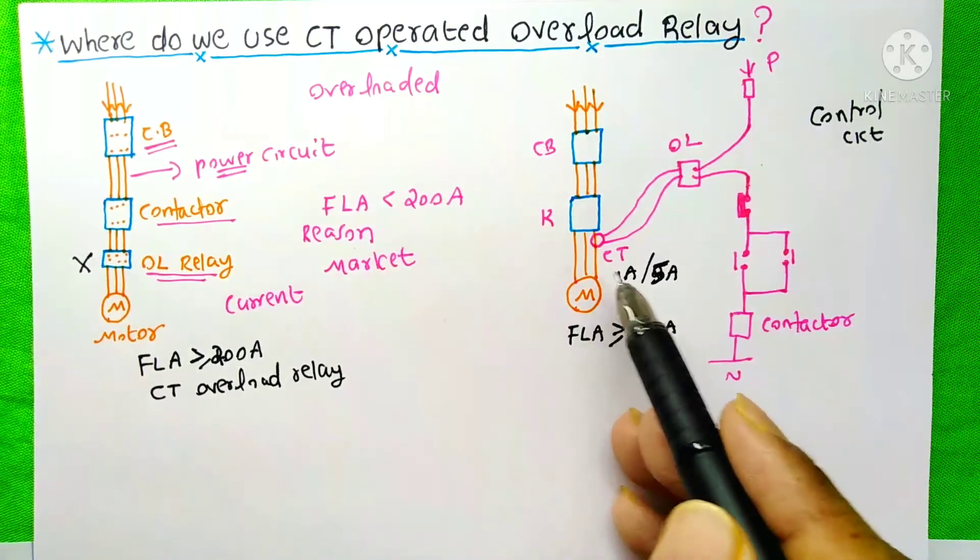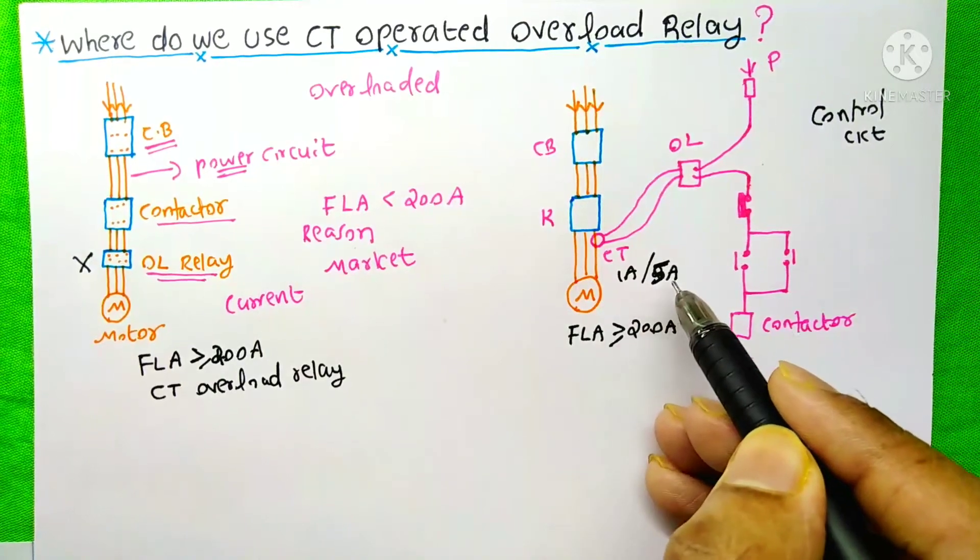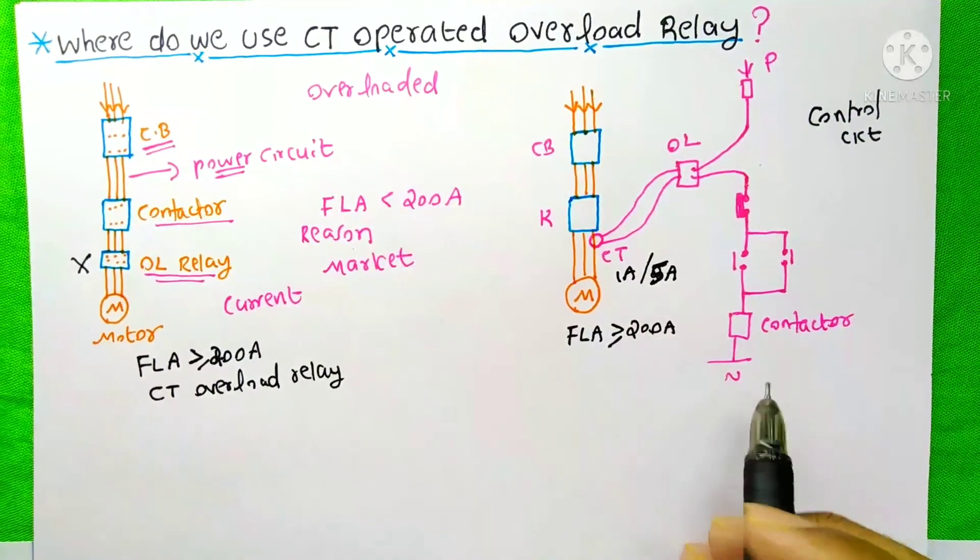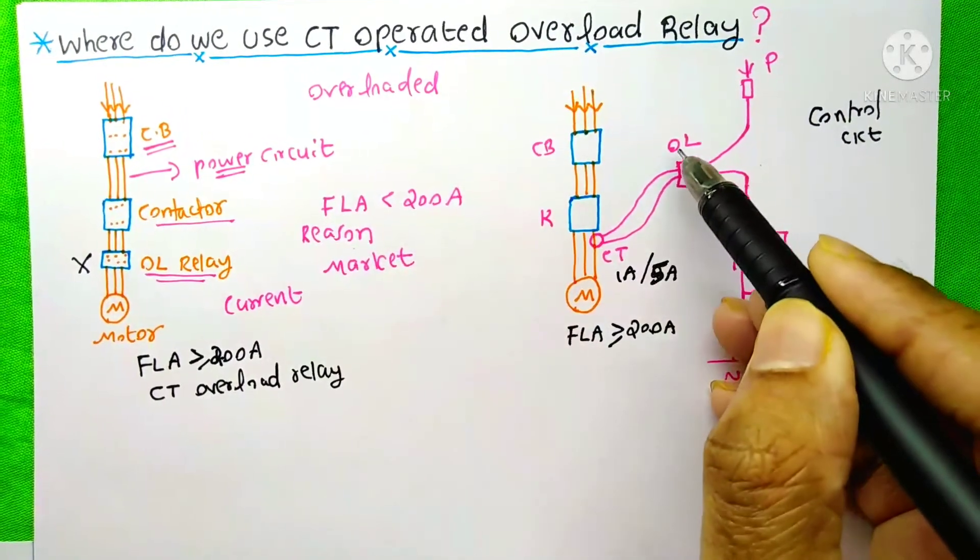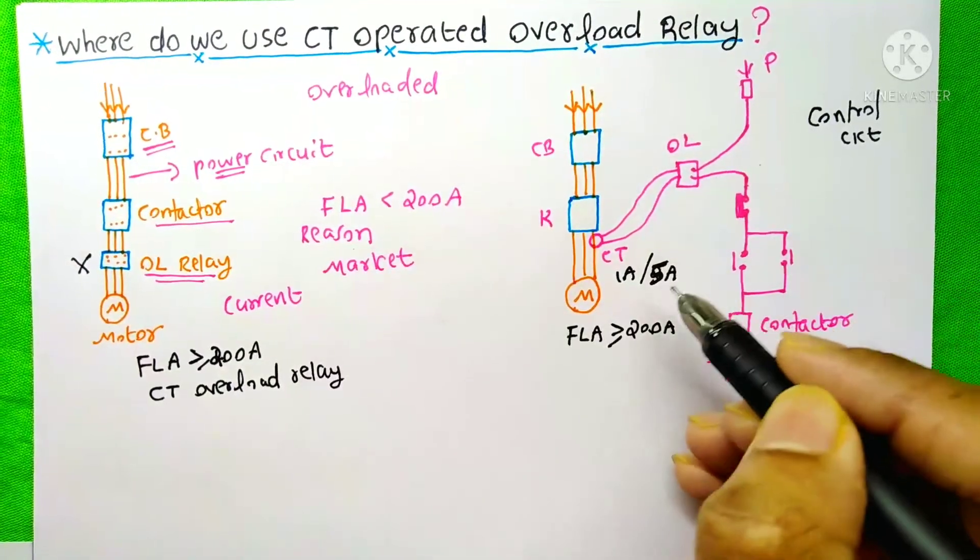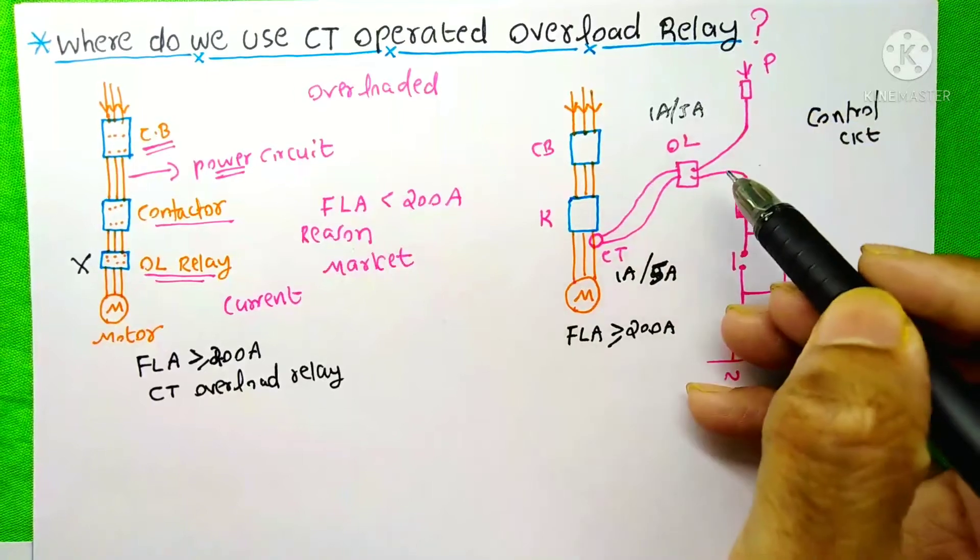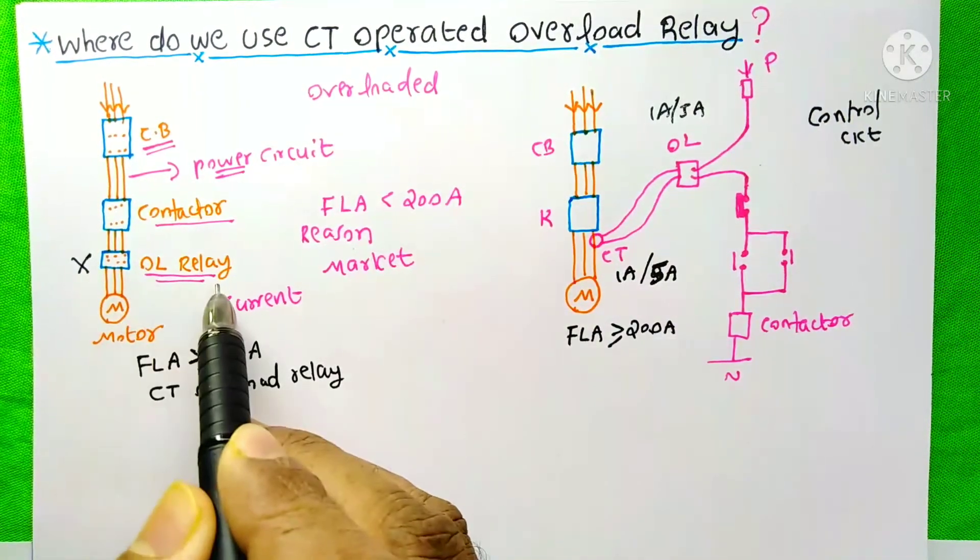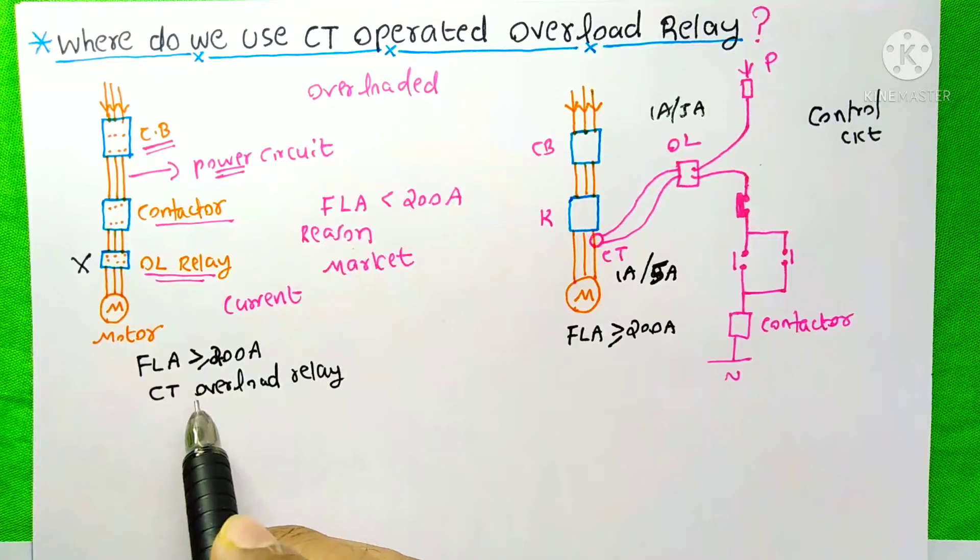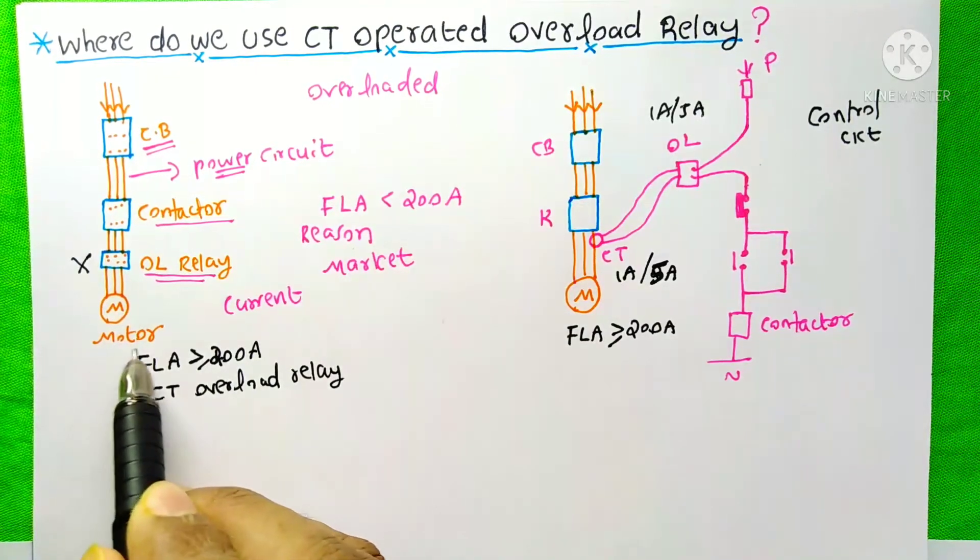This CT's secondary current may be 1 ampere or 5 ampere. Here we need to give an overload relay in the range of 1 ampere or 5 ampere, it's enough. But in this case, this overload relay must be a range of full load ampere of this motor.